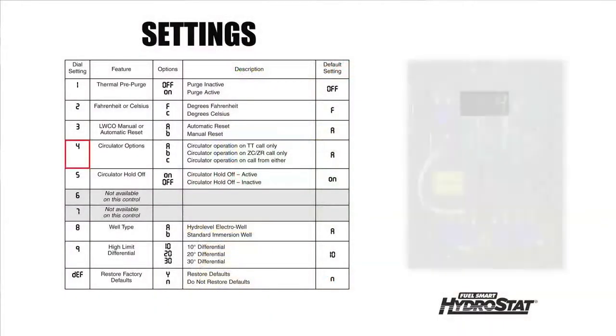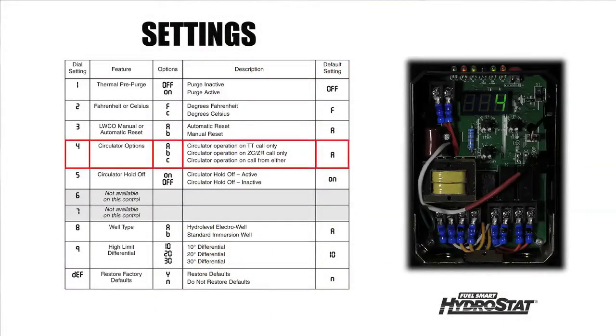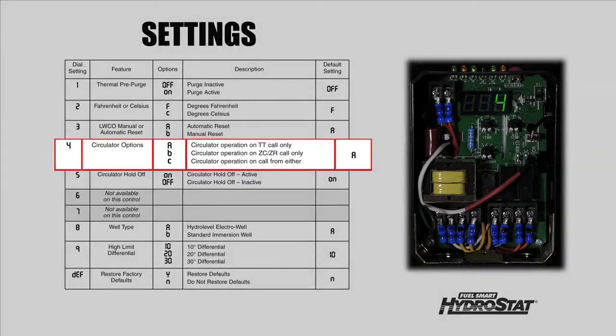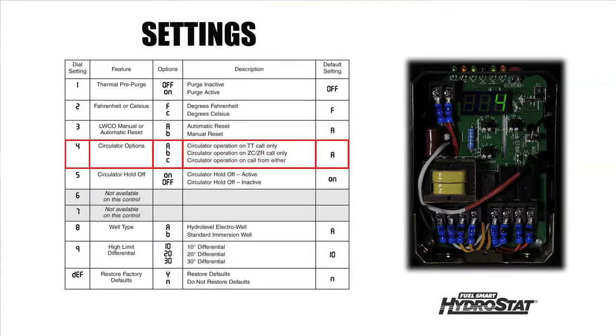Option four allows you to set which inputs will activate the circulator contacts. The options include A, any call to TT, B, a call to ZCZR, or C, a call to either TT or ZCZR. The default is set to TT. This feature provides wiring flexibility when adding zones to existing installations.